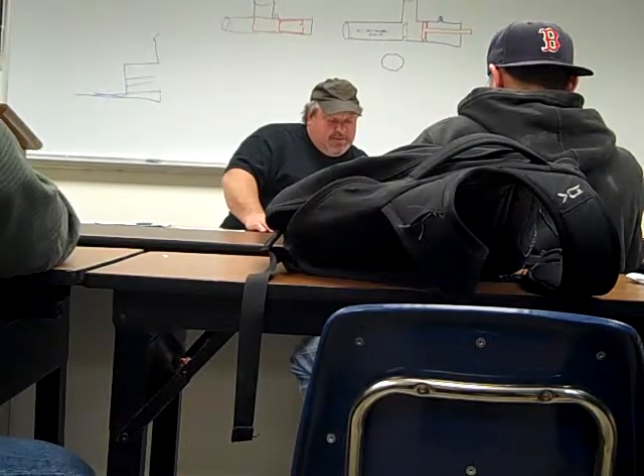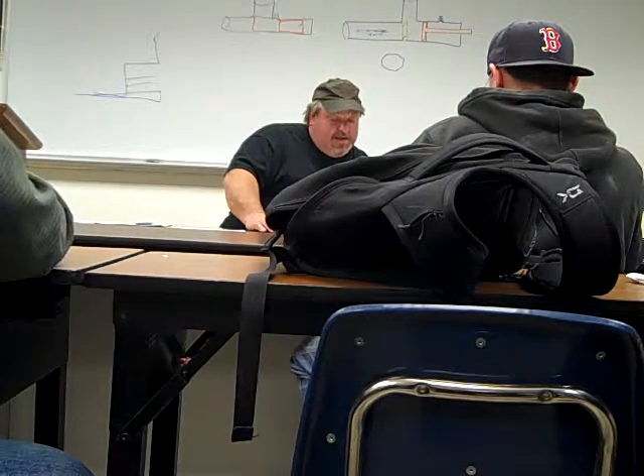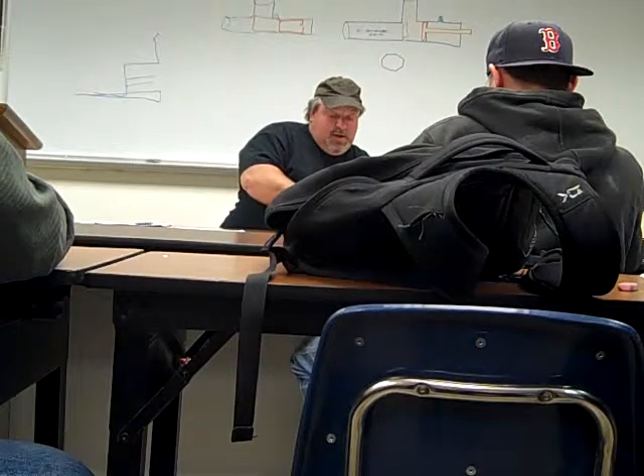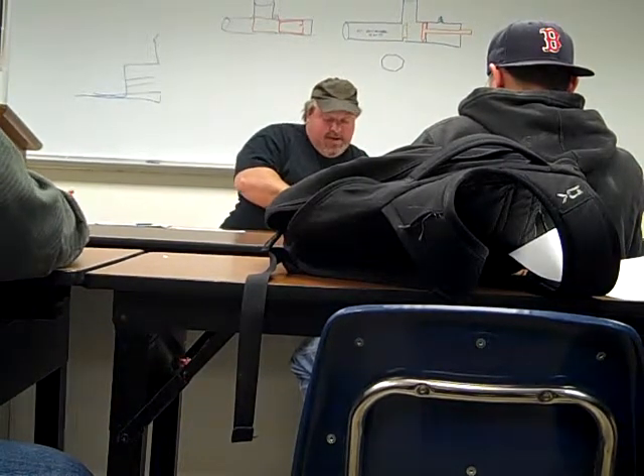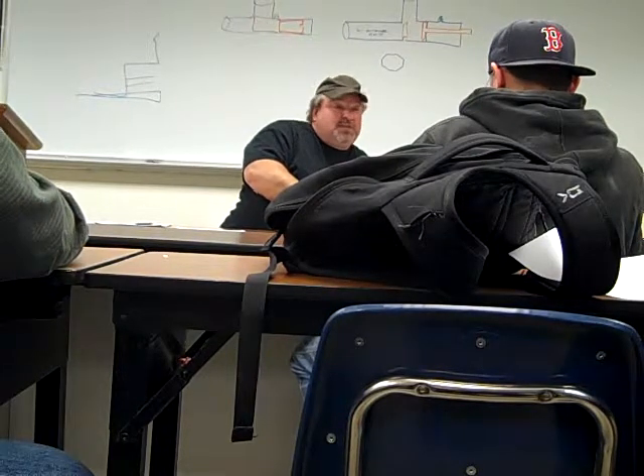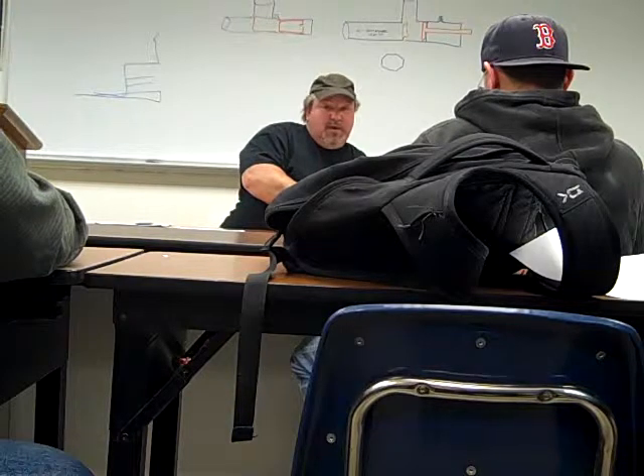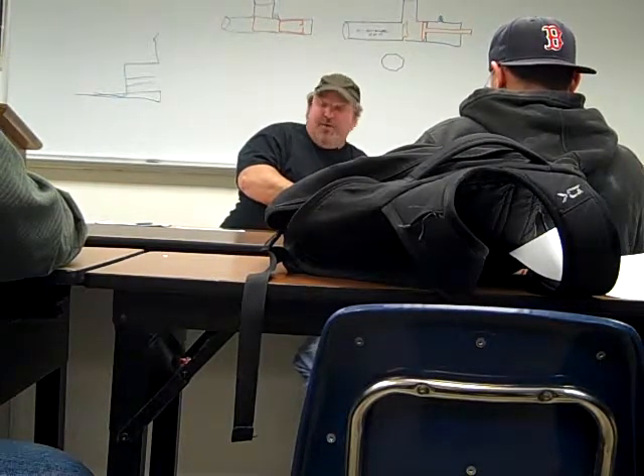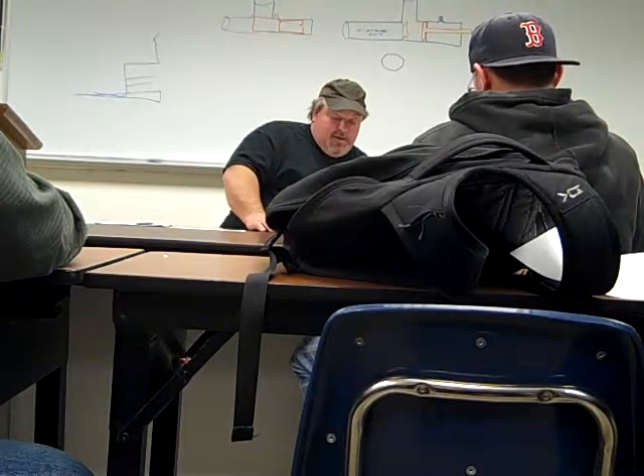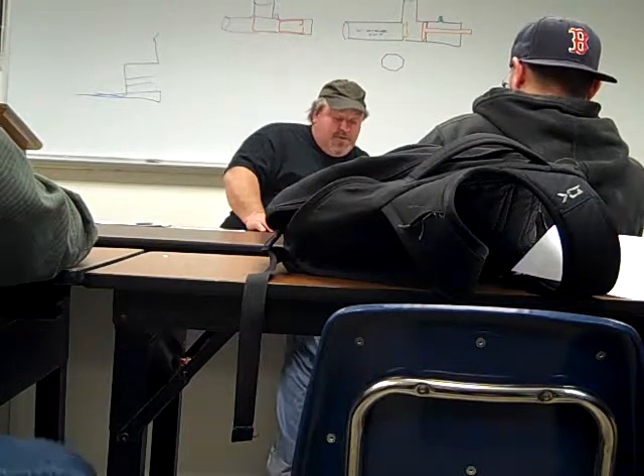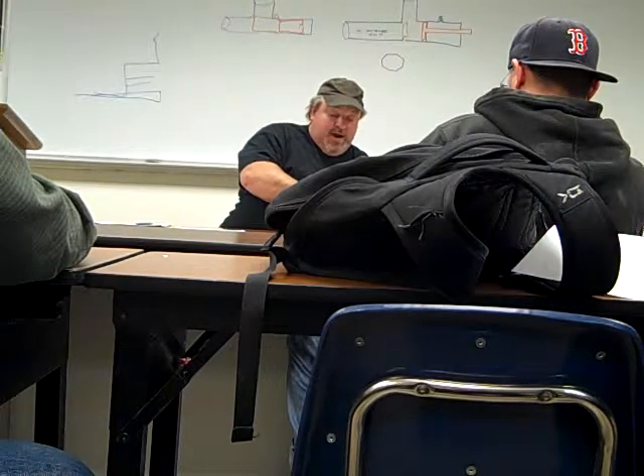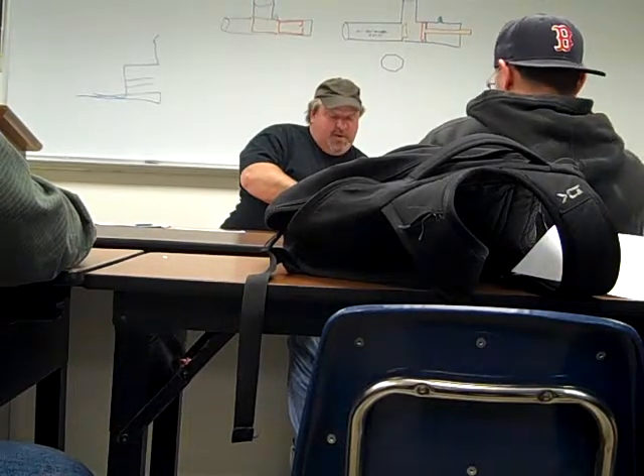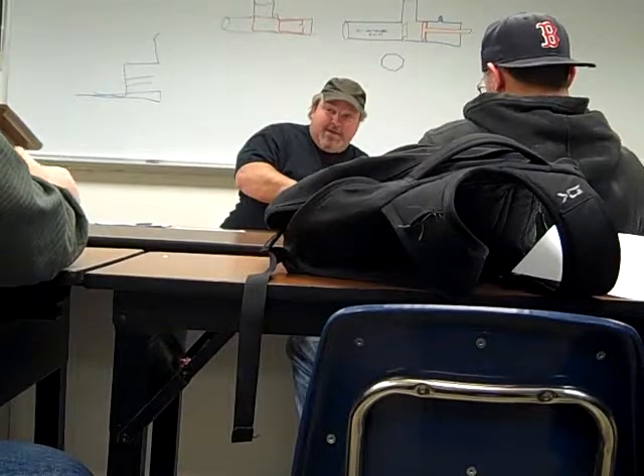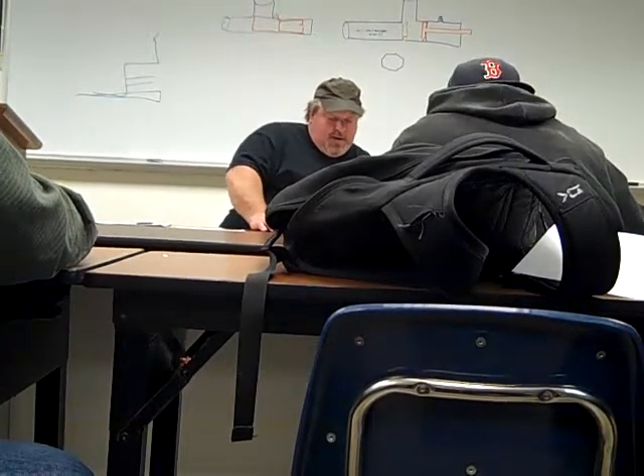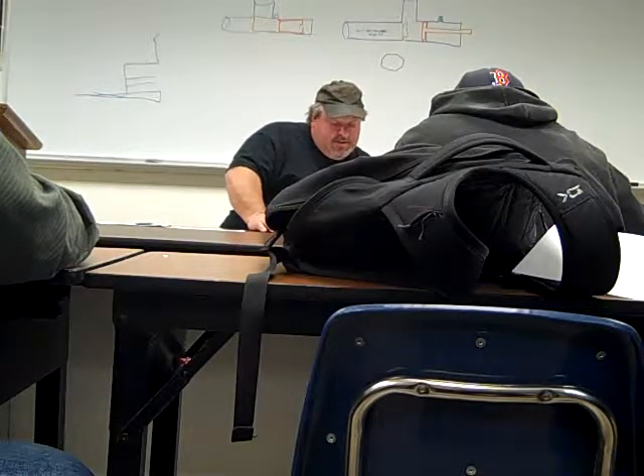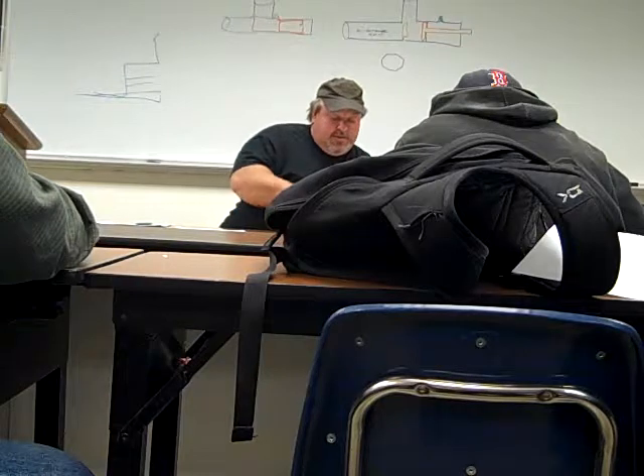HCFC-22 appliances or isolated components of such appliances normally containing less than 200 pounds of refrigerant: equipment manufactured before 1993, you just had to pull it down to 0. You don't have to get it down to any inches of mercury, anything like that. After 93 is 0, so you're good there. HCFC-22 appliances containing more than 200 pounds of refrigerant: before 93, you had to pull it down to 4 inches of mercury. After 93 equipment, it's going to pull down to 10 inches of mercury. Other high pressure appliances containing less than 200 pounds of refrigerant, again, you're at 4 and 10.